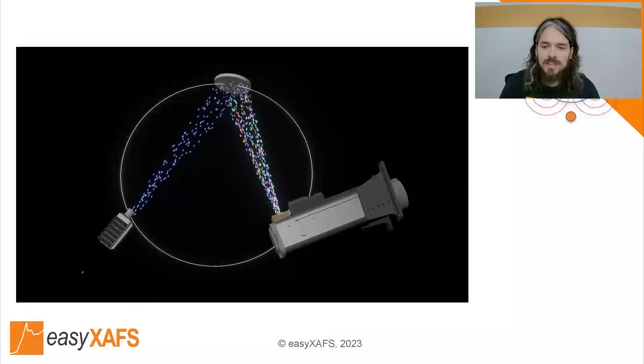Bringing that back into the context of the instrument, here we have a picture with the components illustrated. At a single position, the broadband 0 to 40 keV X-rays are generated by the X-ray tube, and then they're diffracted by the crystal analyzer and come back to the detector with a narrow bandwidth. Here schematically, that's 8,000 eV plus or minus around half an eV. As shown in the animation, we change the angle between the X-ray tube and the detector, so the diffracted energy changes, and then we go step by step, with single acquisitions at each step, to build the X-ray absorption spectrum.